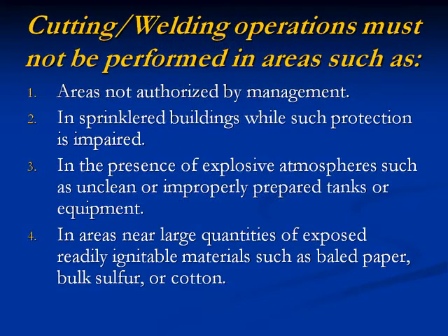Cutting and welding operations must not be performed in areas such as: 1. Areas not authorized by management. 2. In sprinklered buildings while such protection is impaired. 3. In the presence of explosive atmospheres, such as unclean or improperly prepared tanks or equipment. 4. In areas near large quantities of exposed, readily ignitable materials, such as baled paper, bulk sulfur, or cotton.